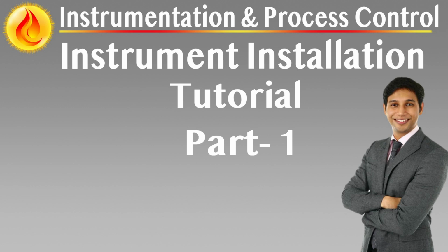Instrumentation and support engineering. Instrumentation must be mounted on dedicated supports that account for thermal movement, process vibration, and insulation compatibility. For remote-mounted devices, impulse lines should be short, sloped 1:5, and free of stagnant pockets. Supports should prevent galvanic corrosion and avoid mounting on grating or insulated pipe unless specially approved. Direct-mounted devices must account for process nozzle stress limits, ensure electronics are shielded from extreme temperature, and consider misalignment risks during dual-tapping installation. Connection integrity and leak prevention strategy.